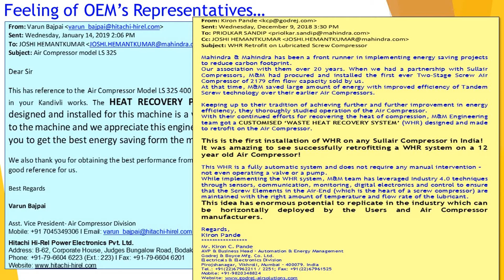Let us see what the internal user has to say. Waste heat which was coming out from our compressors has now been fruitfully utilized, and we are getting around 200 kilowatts of heat from the compressors, with water temperature around 76 degrees centigrade. That water travels from the compressor about 500 to 600 meters and gives out heat to our washing machines. The effectiveness of the washing machines has also improved, along with low maintenance cost.